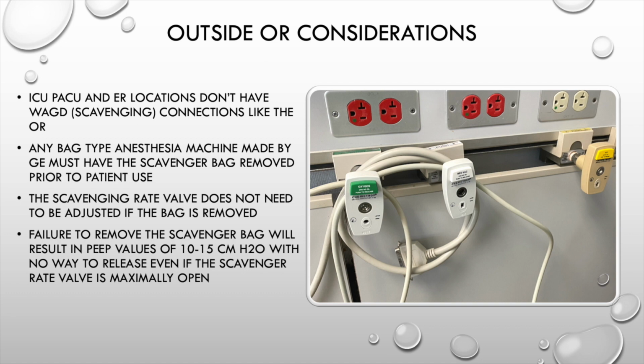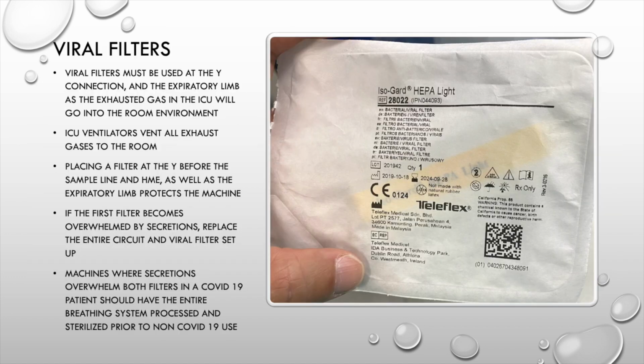If you leave the bag in place and you try to open the valve all the way, you can have as high as 15 centimeters of water pressure of PEEP, and there's no way to release it unless you disconnect the bag, even if the pin valve is maximally opened.